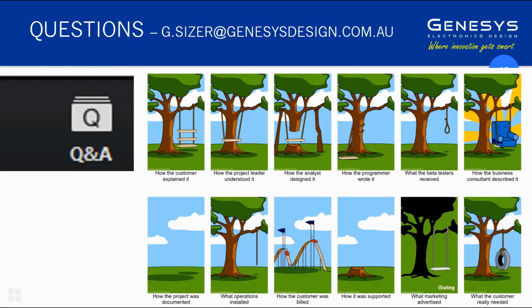underpinning requirement is to ensure safety of the product. And of course, any product on the market needs to be safe for not electrocuting people, for example. But for a medical device, the safety requirements are effectively multiplied in terms of their extent. So looking at electrical safety, we not only have to not electrocute people, but there are requirements to reduce leakage currents to extremely low levels that are much more stringent, for example, than for a normal consumer product.